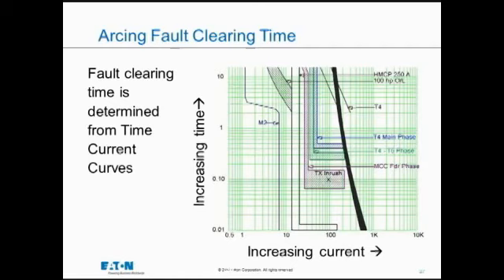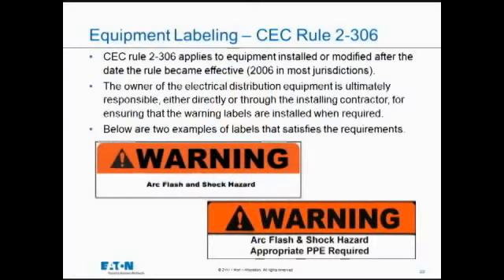Inside of the Canadian Electrical Code, there has been a rule, and the rule is 2-306, that's been around since the year 2006, requiring arc flash hazard warning labels on new installations after that 2006 code was published. And those warning labels, examples of them are shown at the bottom of this slide. It's just a straightforward warning, arc flash hazard. There is no more information other than that required on the Canadian Electrical Code rule.